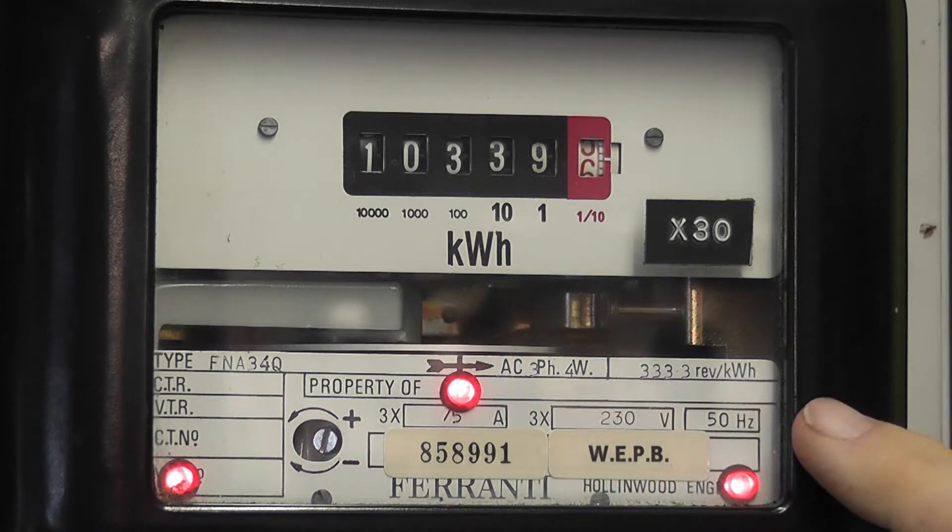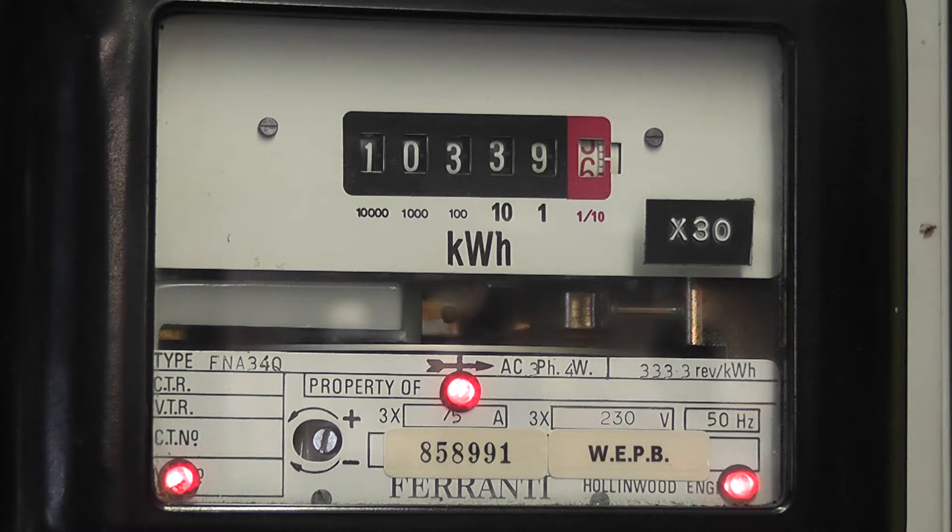Three hundred thirty three point three revolutions per kilowatt hour. It's a 5-amp meter with three times 75 amps, 230 volts, 50 hertz. This meter was used on a 150 to 5 ampere supply, and a multiplier of times thirty was attached to the meter.